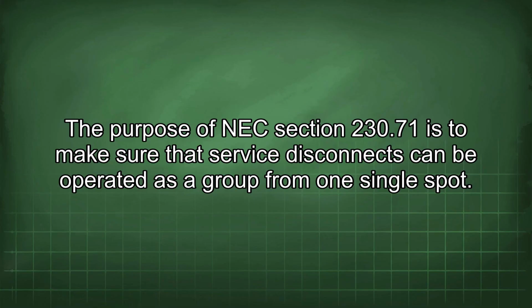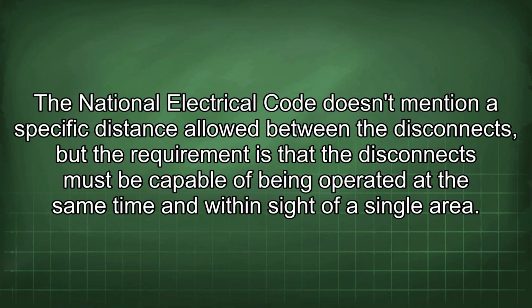The purpose of NEC Section 230.71 is to make sure that service disconnects can be operated as a group from one single spot. The National Electrical Code doesn't mention a specific distance allowed between the disconnects, but the requirement is that the disconnects must be capable of being operated at the same time and within sight of a single area.